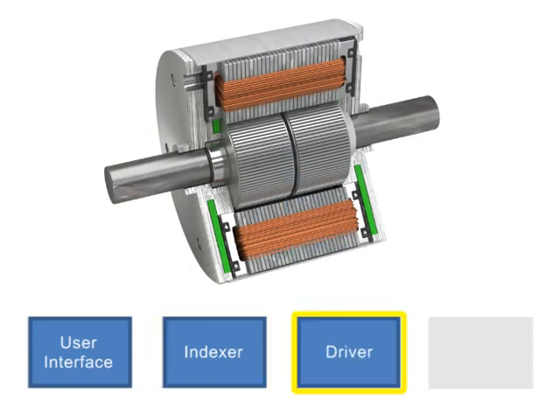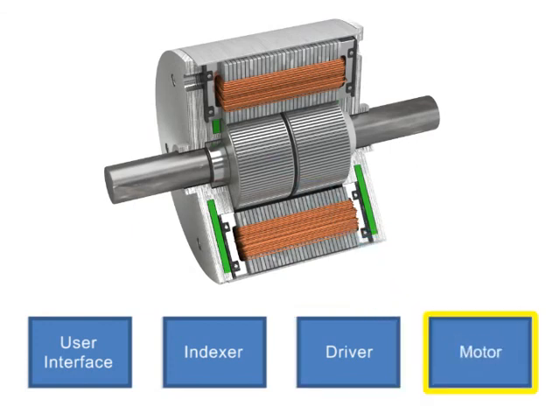The driver then takes the data from the indexer and provides current pulses to the motor. The number of steps the motor turns is equal to the number of pulses transmitted to the driver. The stepper motor is a brushless electric motor that converts pulses into mechanical shaft rotation.